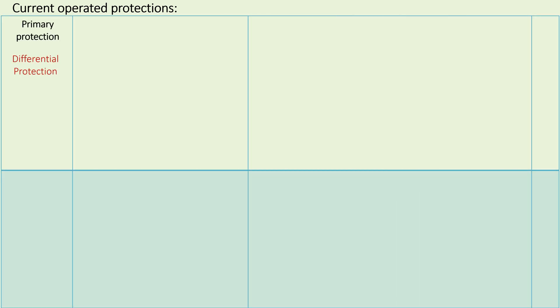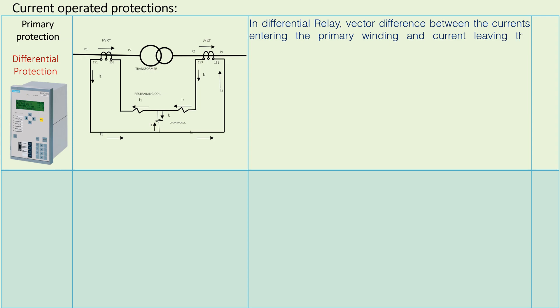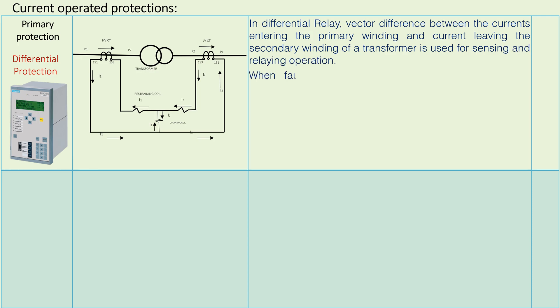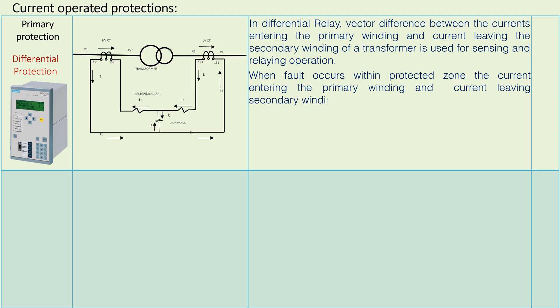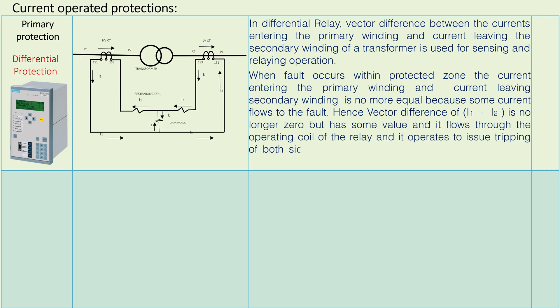Current operated protection — Differential Protection: In a differential relay, the vector difference between the current entering the primary winding and the current leaving the secondary winding of a transformer is used for sensing and relaying operation. When a fault occurs within the protected zone, the current entering the primary winding and the current leaving the secondary winding are no longer equal because some current flows to the fault. Hence the vector difference of I1 minus I2 is no longer zero but has some value, and it flows through the operating coil of the relay, which operates to issue tripping of both side circuit breakers.